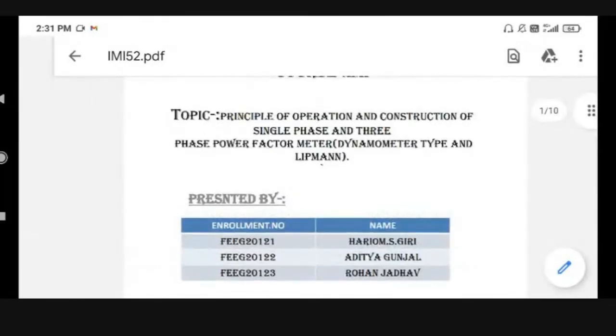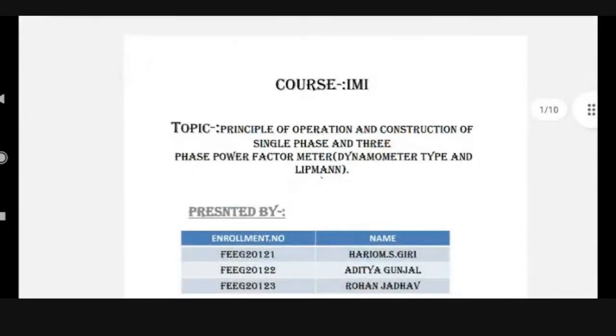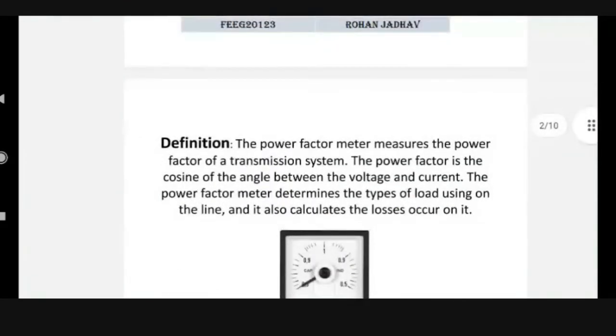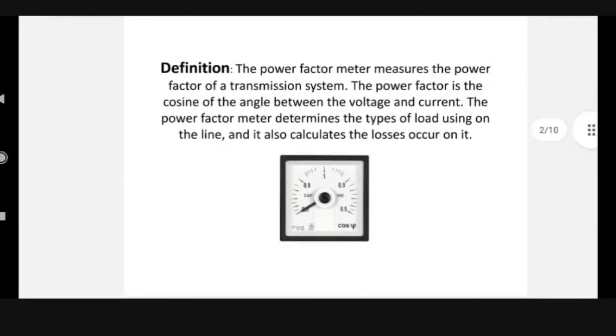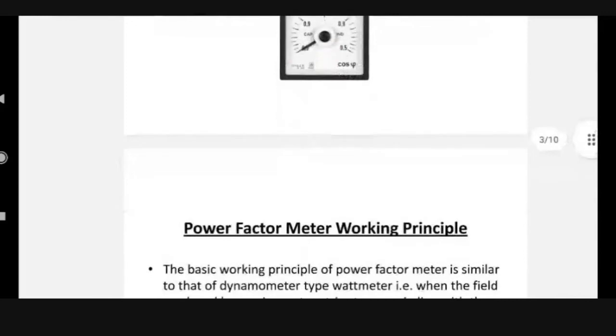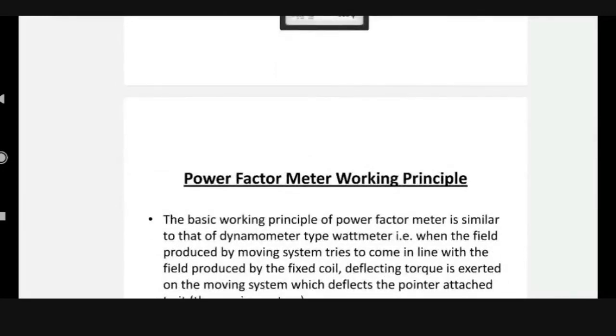Group number 8, topic: principle of operation and construction of single phase and three phase power factor meter. First one, definition. The power factor meter measures the power factor of a transmission system. The power factor is the cosine of the angle between the voltage and current. The power factor meter determines the type of load used on the line, and it also calculates the losses that occur on it.